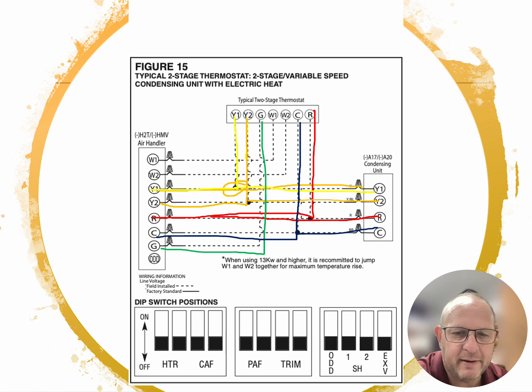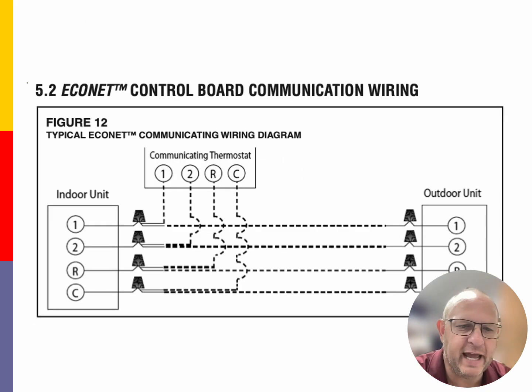Now, that is a two-stage unit. The next thing we're going to be looking at is a communicating system. Now, usually communicating systems are four wires. Some of them are labeled 1, 2, 3, 4. Some of them are labeled 1, 2, RC. But however they're labeled, you're gonna have to hook up the wires to the exact terminals on these communicating units, or they will not communicate with each other. The thermostat communicates with the indoor unit. The indoor unit communicates with the outdoor unit.